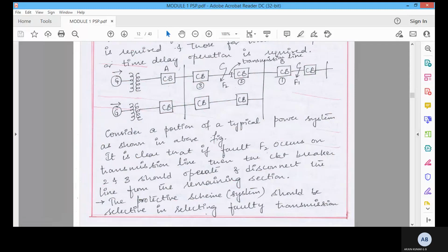Okay, and the third one is sensitivity. This is very important. The sensitivity is very important. The protective relay should operate when the magnitude of the current exceeds the preset value. This value is called the pickup current.